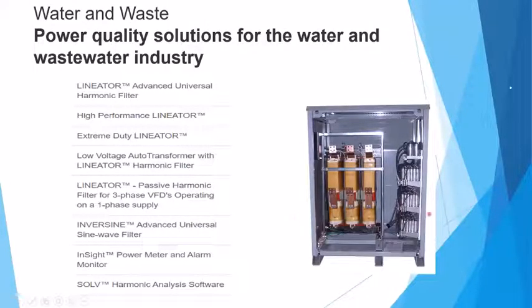But back to the requirements of noise and filtering. So not only do you get harmonic noises from that pulsing on the input, so you have to put a lot of times that link choke that I talked about earlier, or the line reactor, but you've got to put something in front to basically slow that semiconductor diode from just instant, because when it gets power, it instantly shoves it into the capacitor. So it's important that you also, a coil in the circuit resists change, a capacitor accelerates change.